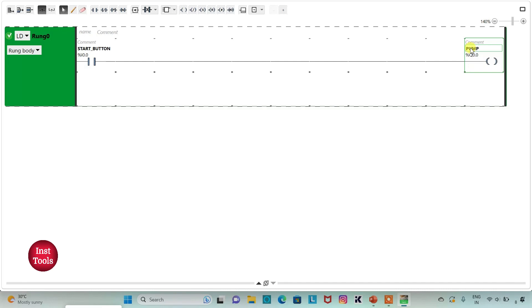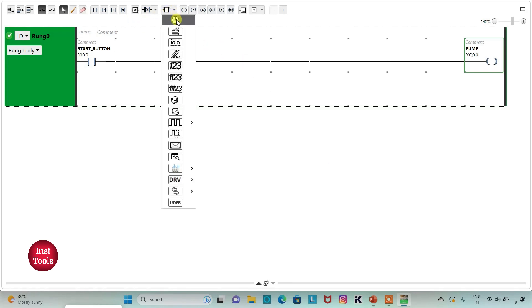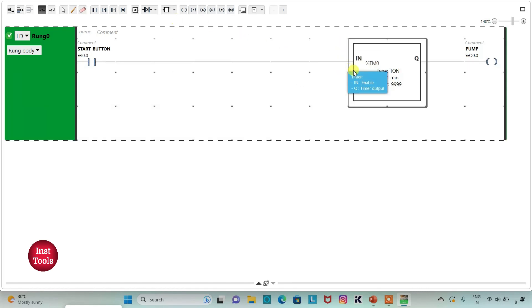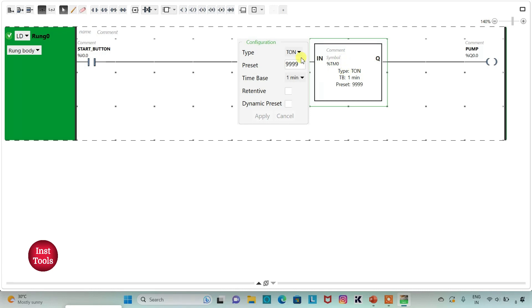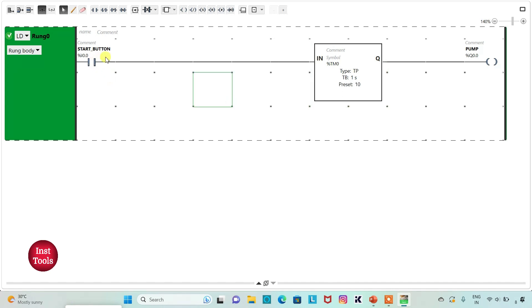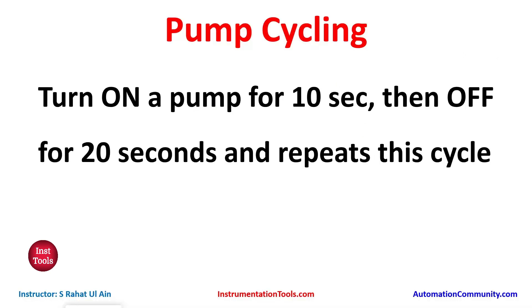Then I will insert a timer here and select type as TP. I will change time base to second and then 10, then click on apply. So when start button is turned on, pump will turn on. Pump will be on for 10 seconds, then off for 20 seconds, and repeat this cycle. It should turn off by its own after 10 seconds, and then after 20 seconds it should turn on for 10 seconds, and this cycle should repeat.